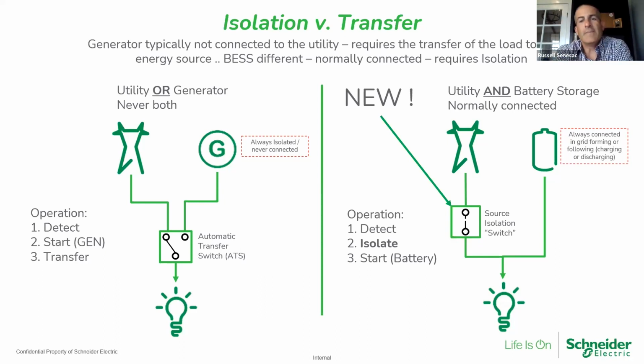It's really about making sure you fundamentally understand the difference between a transfer switch and an isolation switch. A transfer switch is one source or the other source. An isolation switch is normally connected, power goes out, open. So this open mechanism is much different than the transfer mechanism.